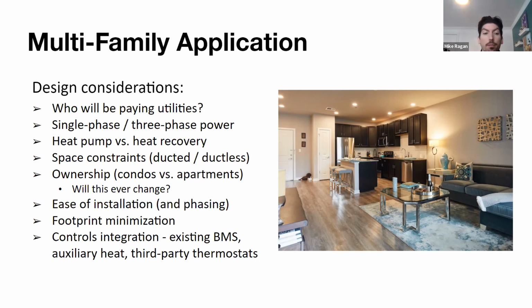Is it BACnet compatible? Do you have auxiliary heat tied in this building? And do you want that to be tied into the VRF or heat pump system, or are you planning on ripping that out? Do you have third-party thermostats? Right? Do you have Nest or Honeywell thermostats that your tenants are all big fans of, and they want that to operate their HVAC equipment? This is all possible. It's all definitely things that we could work with. But these are our day one questions, the first things that we're going to ask before we even start talking about model numbers.